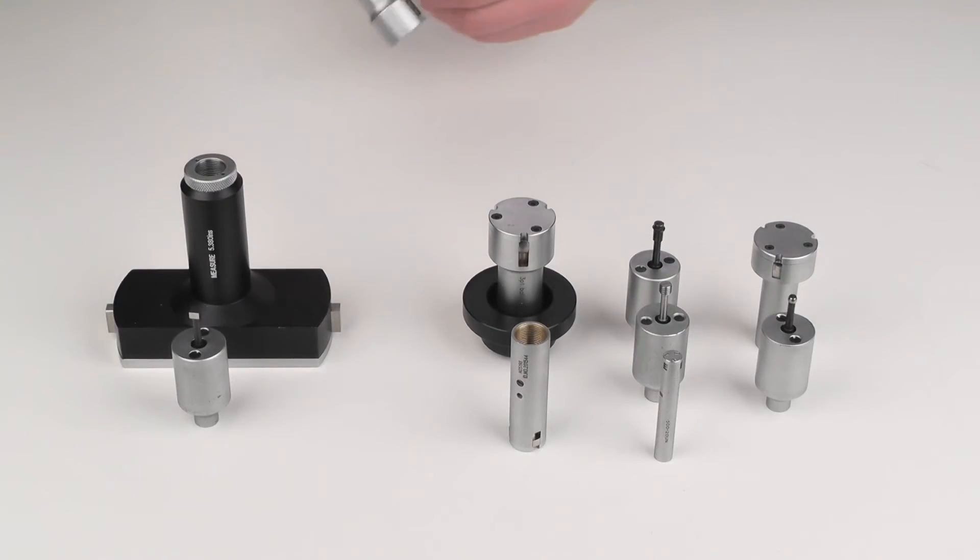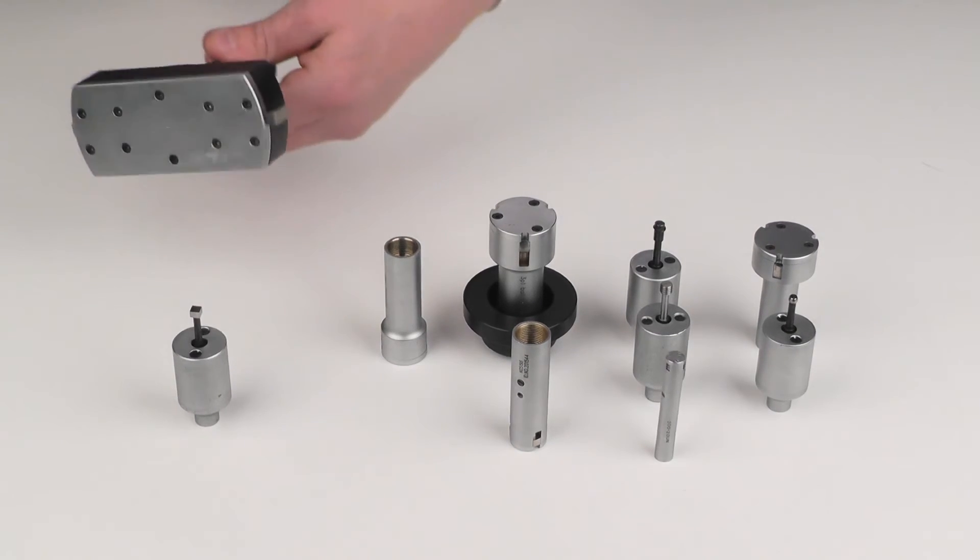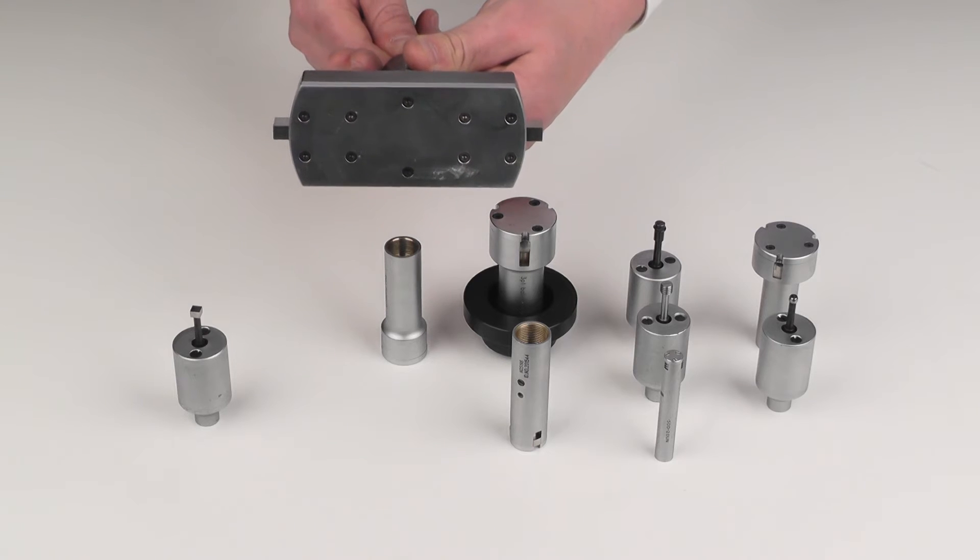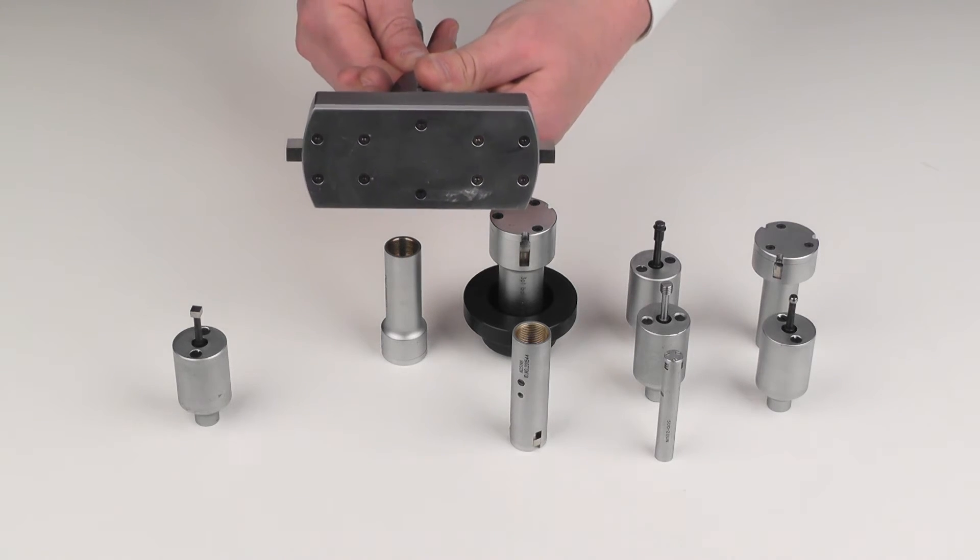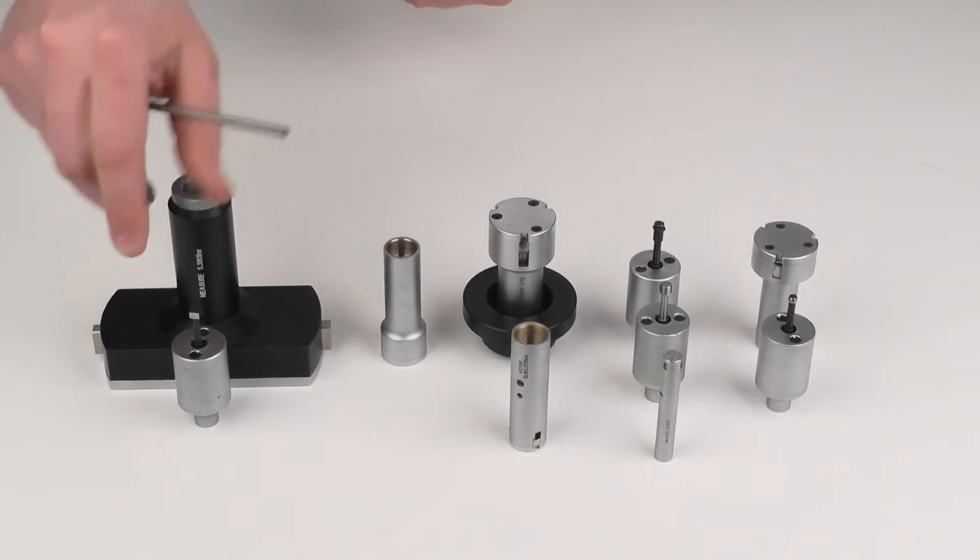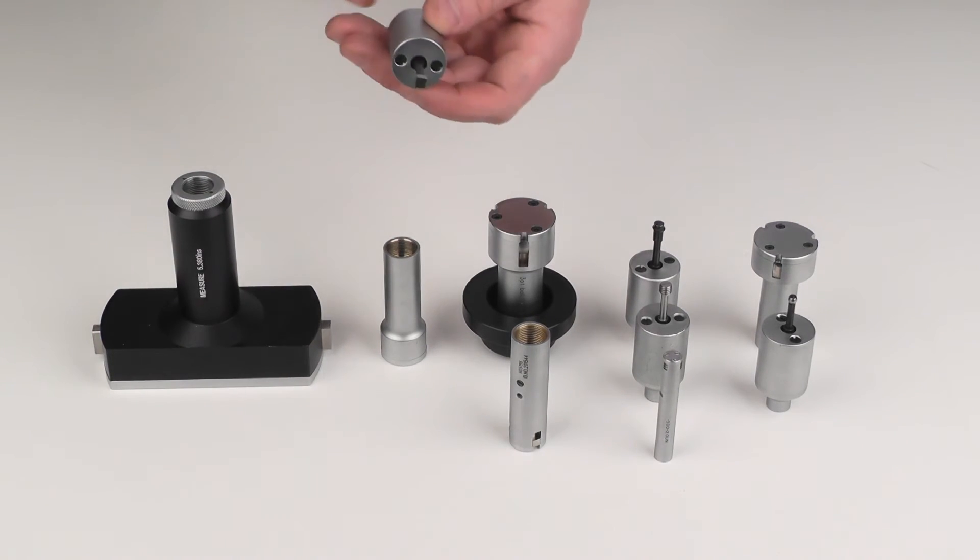And then for slot widths, you would have a square anvil and just two opposing anvils to check the width of a slot. Here we have a very large slot and then a much smaller one intended for, say, a keyway on a drive shaft.